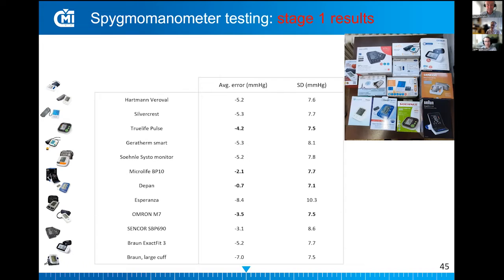As I mentioned, we tested devices with 85 signals, all of them, and the results were calculated as average error and standard deviation. The European standard says that in order to pass the clinical trial, the device should perform with an average error of 5 millimeters of mercury, plus minus 5 millimeters of mercury, or lower, and a standard deviation of 8 millimeters of mercury or lower.